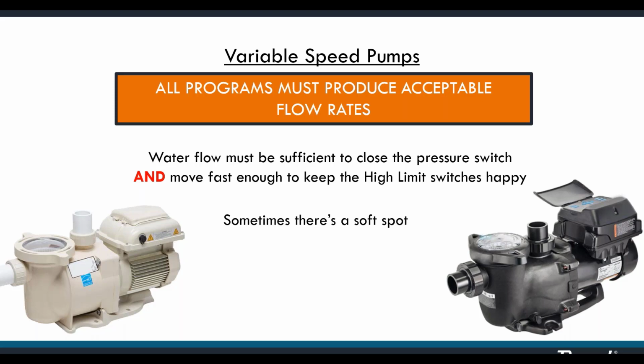During setup, run the heater with the pump at the lowest speed programmed for 10 or 15 minutes to make sure this doesn't happen. And then do that same test with the plumbing set to spa. Remember, the hydraulics are different on the spa. So if you've got a pool spa combo, flip those valves around, let the pump run and the heater run in spa mode for 10 minutes or so just to make sure we're not going to have a problem.